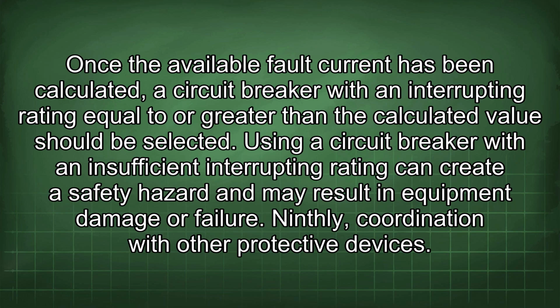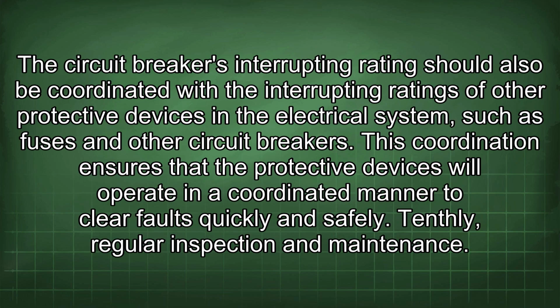Using a circuit breaker with an insufficient interrupting rating can create a safety hazard and may result in equipment damage or failure. Ninthly, coordination with other protective devices. The circuit breaker's interrupting rating should also be coordinated with the interrupting ratings of other protective devices in the electrical system, such as fuses and other circuit breakers. This coordination ensures that the protective devices will operate in a coordinated manner to clear faults quickly and safely.